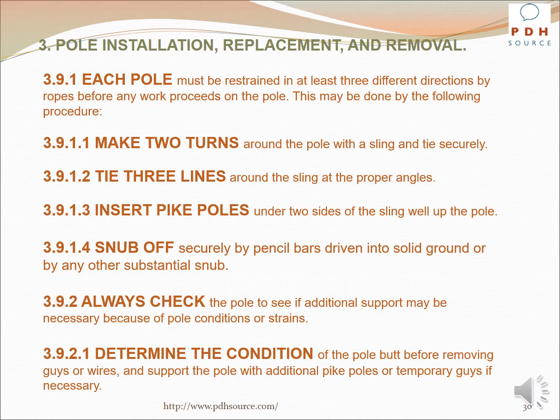Each pole must be restrained in at least 3 different directions by ropes before any work proceeds on the pole. This may be done by the following procedure. Make 2 turns around the pole with a sling and tie securely. Tie 3 lines around the sling at the proper angles. Insert pike poles under 2 sides of the sling well up the pole. Snub off securely by pencil bars driven into solid ground or by any other substantial snub.